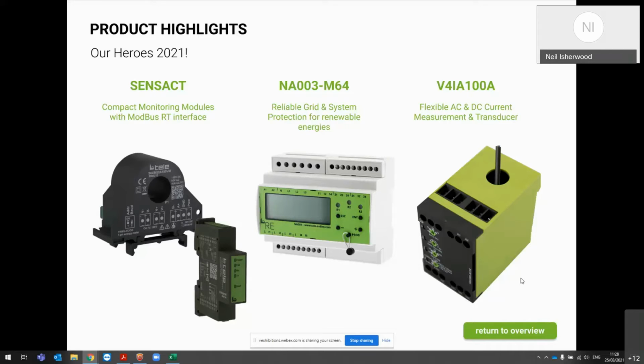Then we've got the NA003 M64. This is a grid disconnection device. It monitors voltage and frequency. What it does is check the network, and if the network is okay to accept the power you're feeding into it, it allows you to, but if it's not, it disconnects.